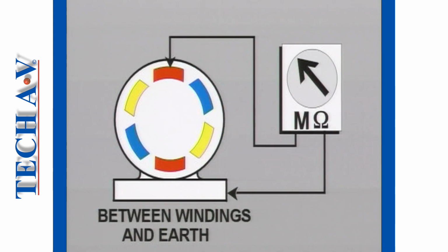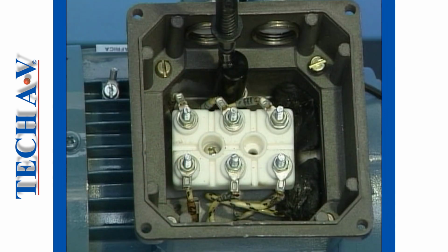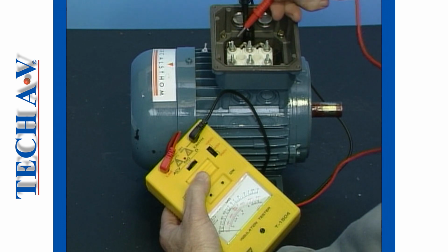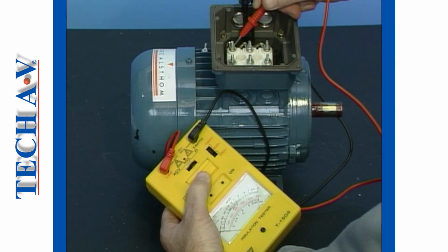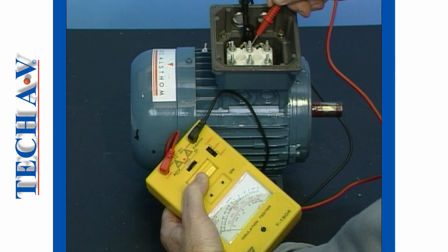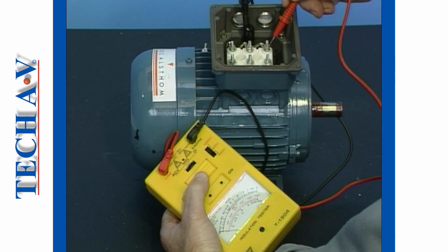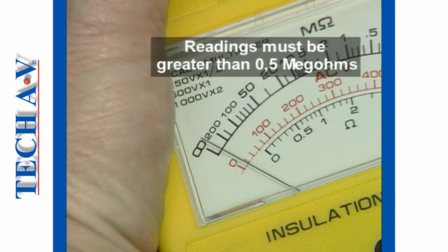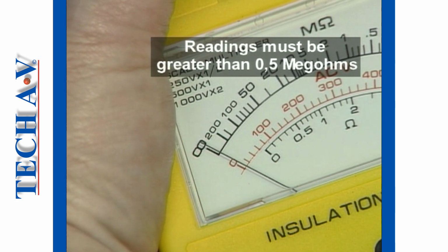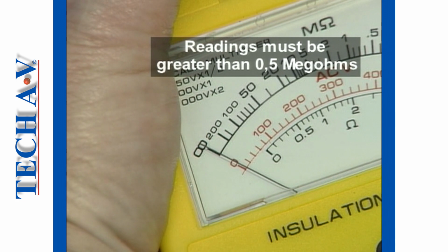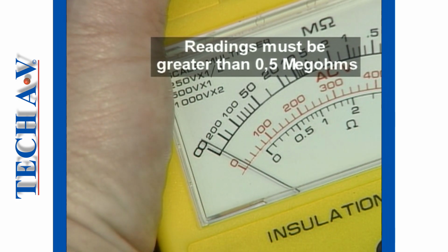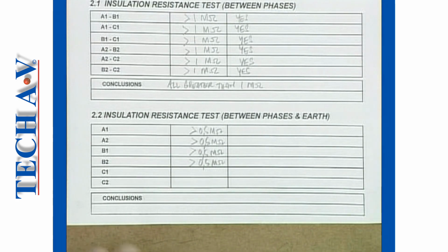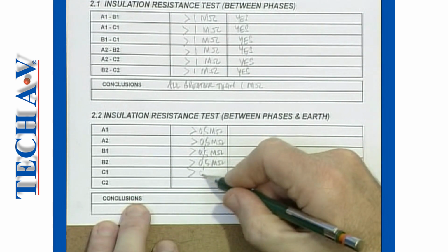Now we move on to test the insulation resistance between the windings and the motor frame or earth. Begin by attaching a test lead to the frame of the motor. Then, with the other test lead, test the insulation resistance between each winding in turn. To meet acceptable standards, all the resistance readings obtained must be greater than 0,5 megohms. Record each measurement and your comments on the checklist.